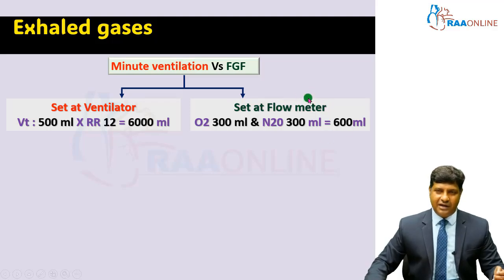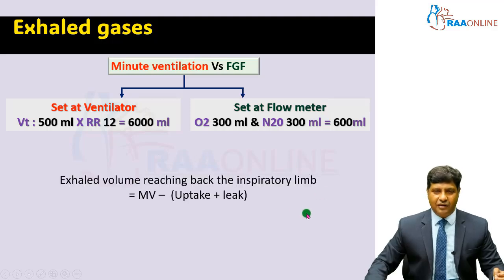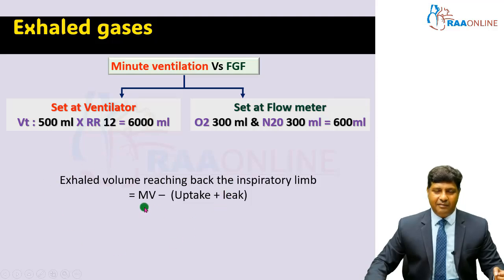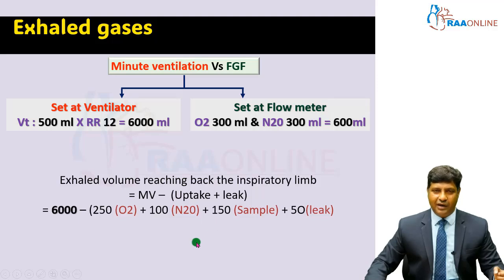In low flow anaesthetic technique, for example, if you set oxygen at 300 ml and nitrous oxide at 300 ml, your fresh gas flow is going to be 600 ml. But the patient's minute volume is 6000 ml. So, in that instance, what volume is going to reach back the inspiratory limb after absorption of carbon dioxide? After the minute volume enters the patient's lungs and comes back, whatever is taken up is taken up, plus there is some leak. The minute ventilation minus the sum of uptake and leak determines your exhaled volume. For example, if the oxygen uptake is 250 ml and nitrous oxide uptake is 100 ml.